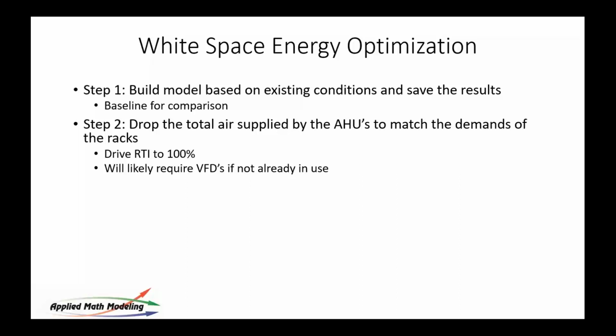I'm going to use terms like RTI. RTI is the return temperature index. It is a ratio of the amount of air the racks need compared to the air handler delivery. The air handler delivery flow is usually too high in most data centers I visit. So this number will be lower than 100 because rack demand is in the numerator.